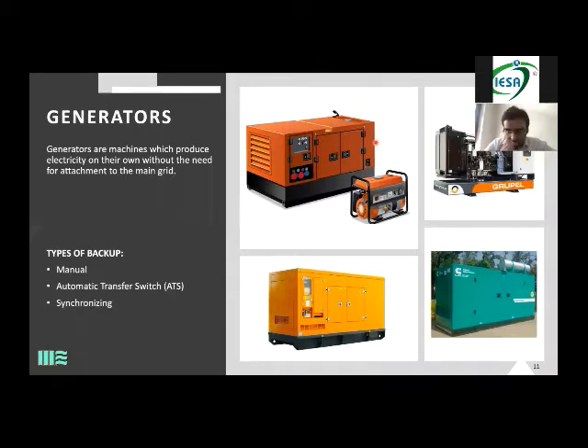Automatic transfer switch: it means automatic. If something happens on site, the genset conks off, or something goes wrong with the generator, the power gets transferred from one genset to another within a span of 1 second. You can set the automatic transfer switch from 1 second to like 3 minutes, but when we are dealing with live events or exhibitions, power is important, so we want the power to come on immediately. So the automatic transfer switch can be set to a 1 second timer.